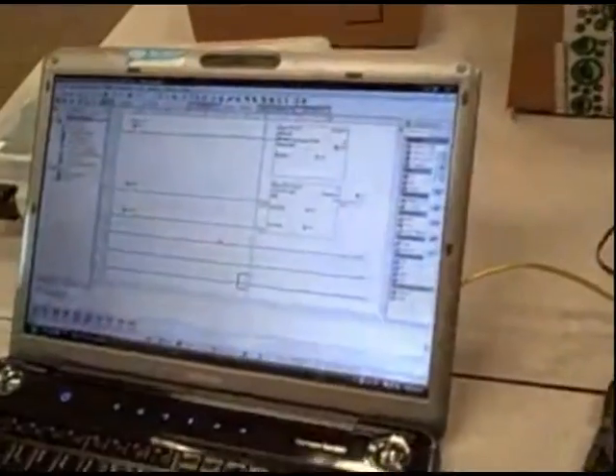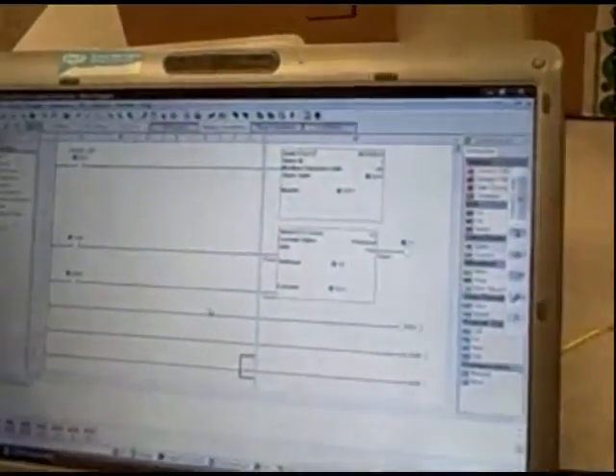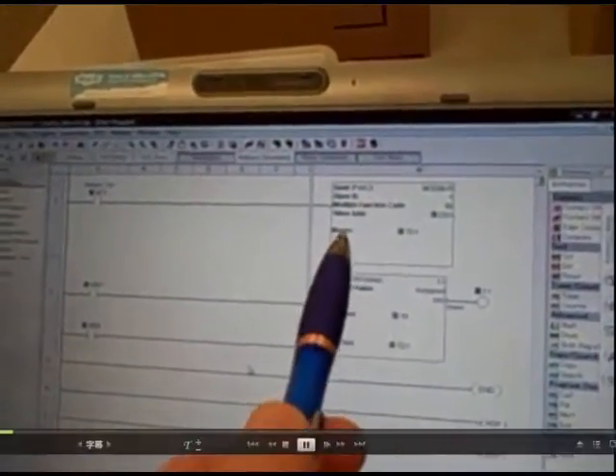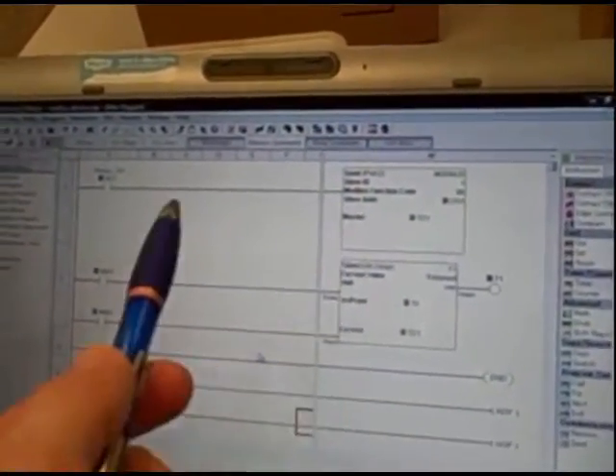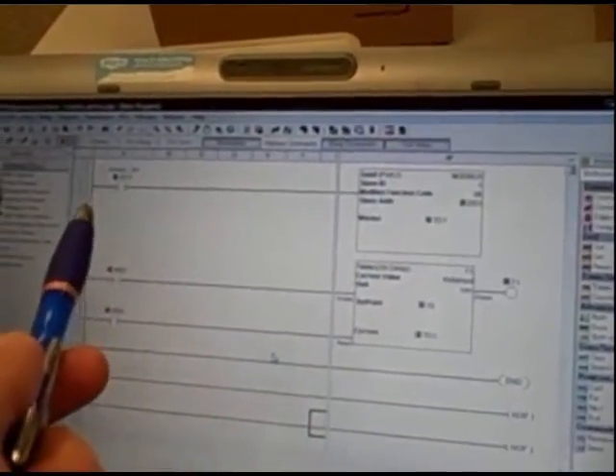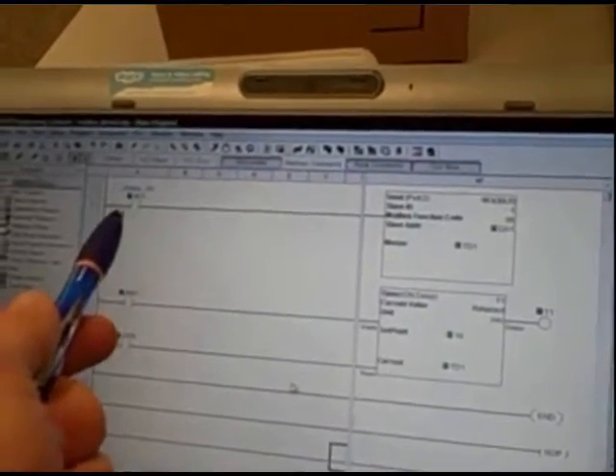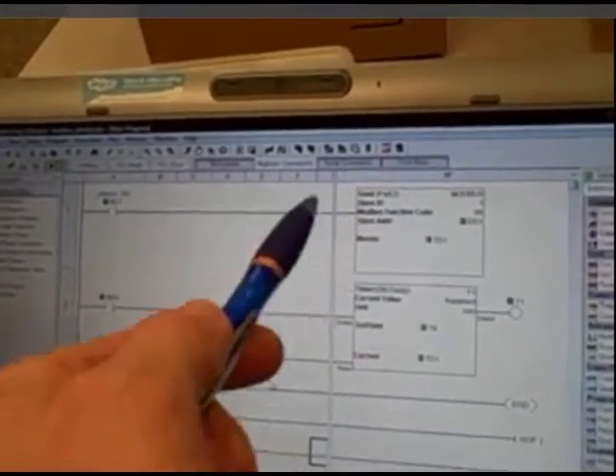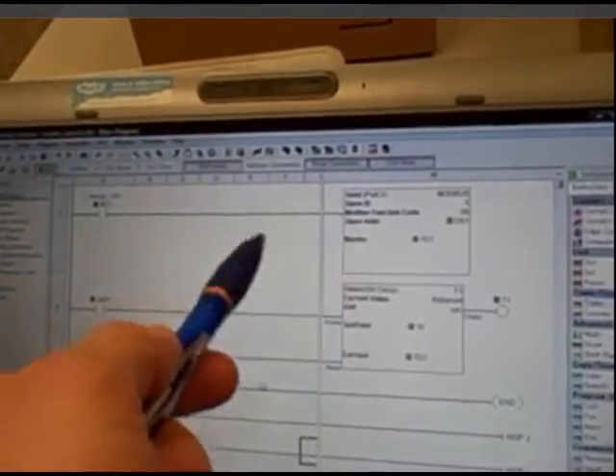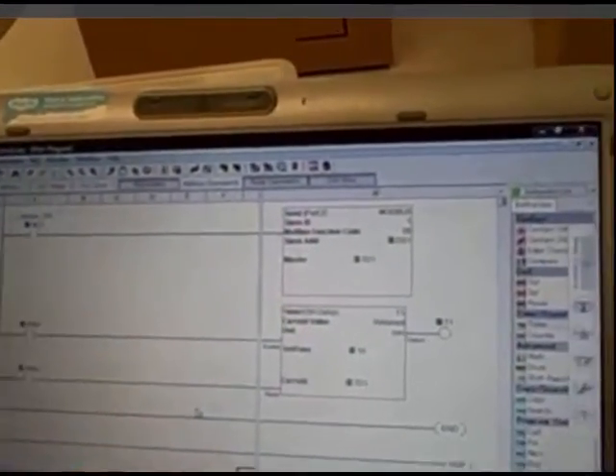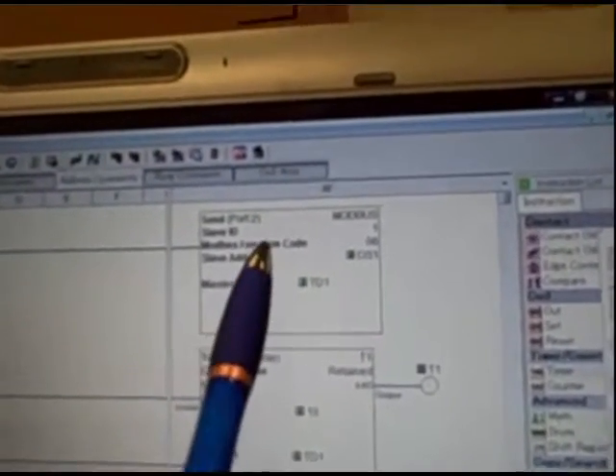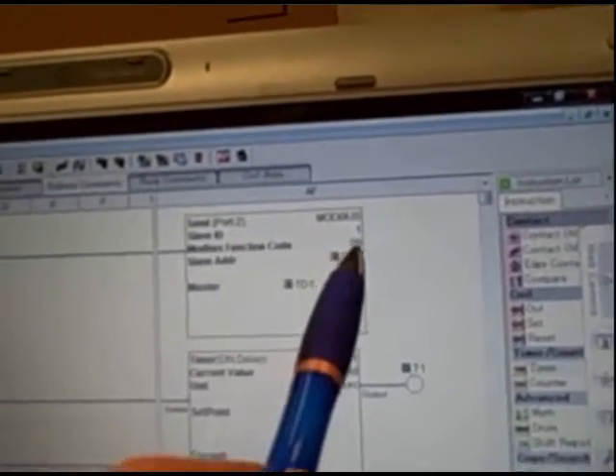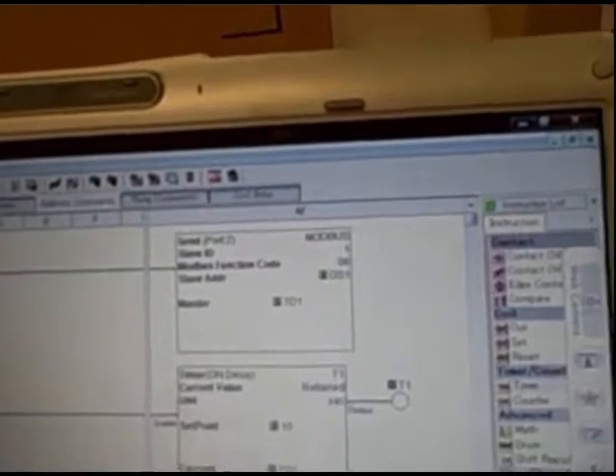In the master PLC we look at the program. We see first there's a Modbus instruction that is always active. We're using a special contact that's always on to continuously energize that box. And in that box it's a Modbus instruction. We are using Modbus function code number six, which is to write a single register.